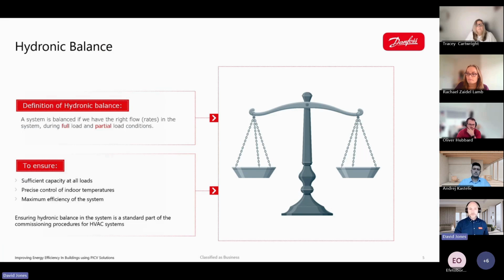Okay, so we move on to hydronic balancing, and we look at the definition of hydronic balancing and what we need to ensure to be able to achieve this. A hydronic system is considered balanced when the correct flow rates are achieved throughout the system, not just at full design load, but also under partial load conditions. In reality, systems rarely operate at 100% load. They spend most of their operational time at part load, so true balance means maintaining control and stability across all operating conditions. Getting this right is fundamental to achieving three things: sufficient capacity at all loads, precise indoor temperature control, and maximum system efficiency.